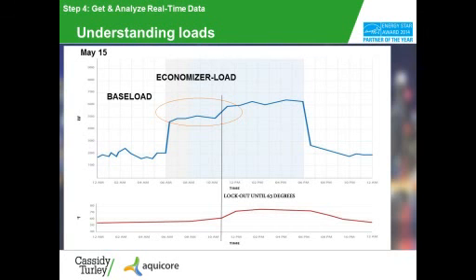Oh, we forgot to talk a little bit about what if we didn't operate on economizer. If the economizer hadn't worked properly and we used mechanical cooling, even though it was 50 degrees outside, there's the savings. That's what our load profile would have looked like if we hadn't been running on economizer. And now we can look at that full load, typical full load right there. Typical day, chiller's on, building's occupied.